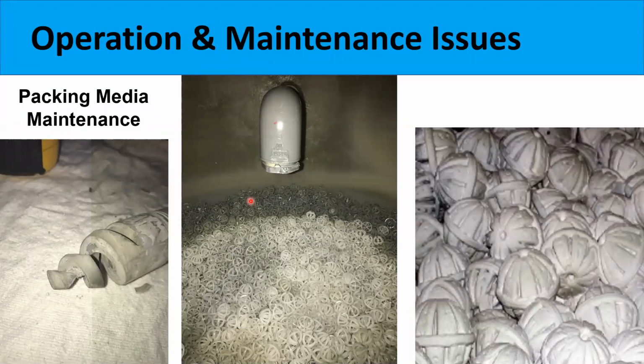And in doing so, you typically need to add a certain amount of fresh water based on evaporation, maybe in your location, and have a continuous amount of blow down that occurs to go to wastewater treatment. If you don't have that, you get a constant buildup of contaminants inside these wet scrubbers that will ultimately lead to a fouled packing situation. And when you get really fouled packing, you're getting reduced airflow, you're getting increased pressure drop, and overall low airflow at the process may lead to some safety concerns about capturing the contaminants at the process. So it's important to keep these things clean.